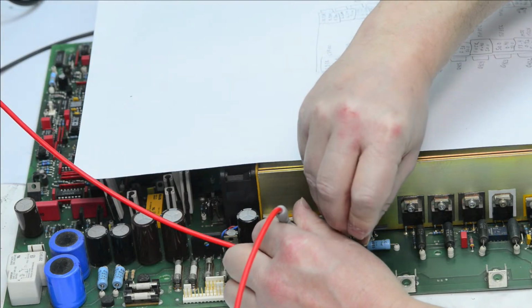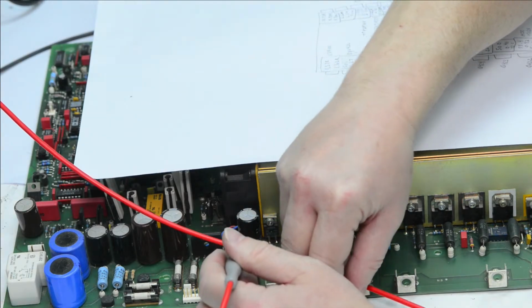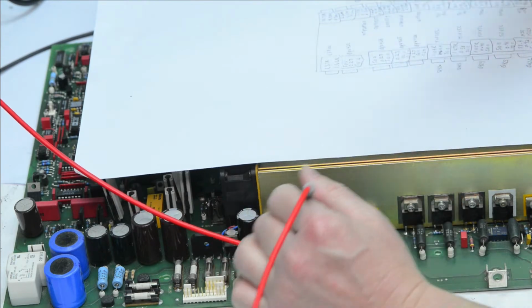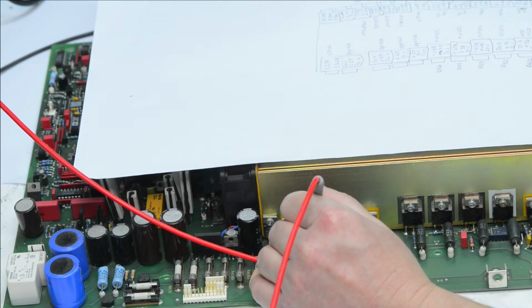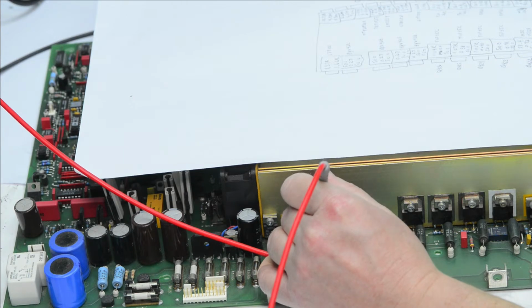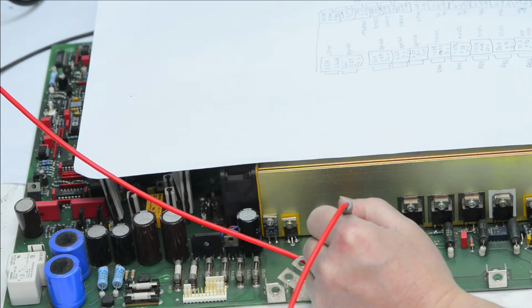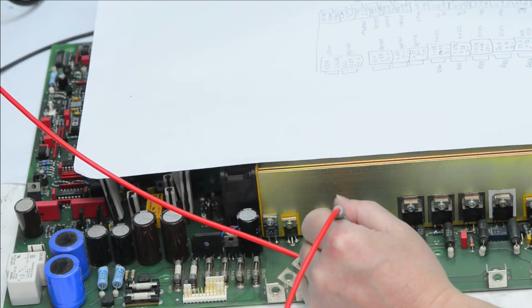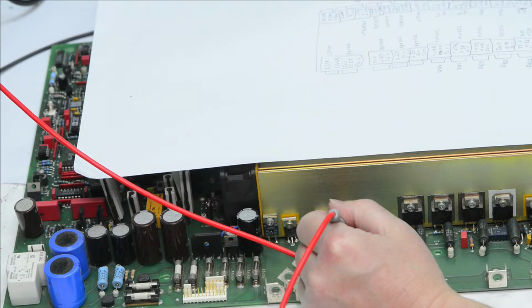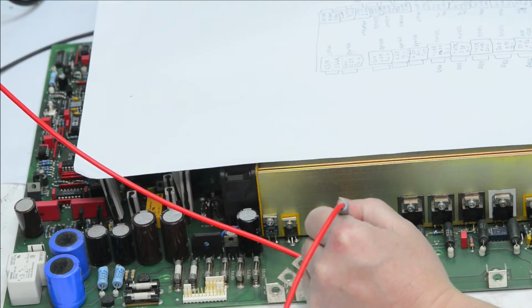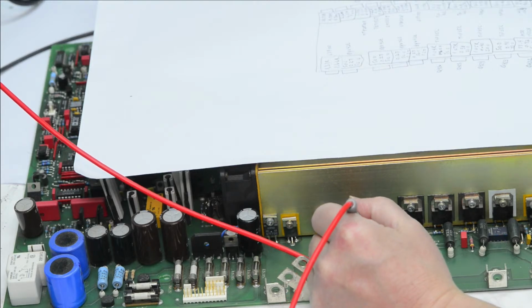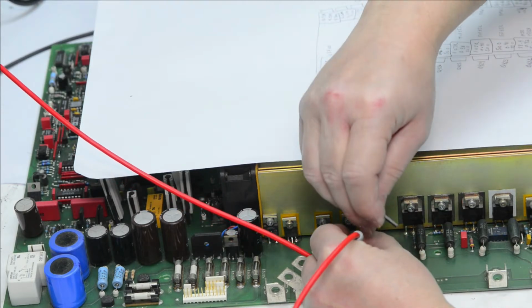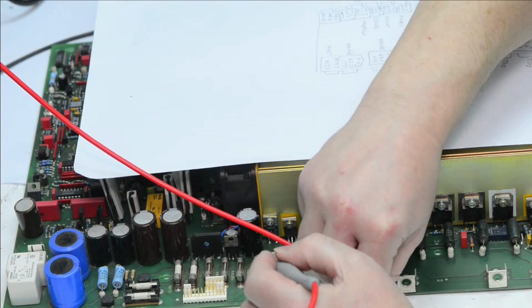They probably implemented it so that if there is something like a power critical fault error, it would lock up the unit and avoid having dangerous voltages flying everywhere and probably destroying components, because you can see here, and also the power jumps. When it starts doing that high voltage or high power test, power goes up to 130 watts or so, but in the normal mode, when it's doing most of the relays clicking, it's about 80 to 90 watts.